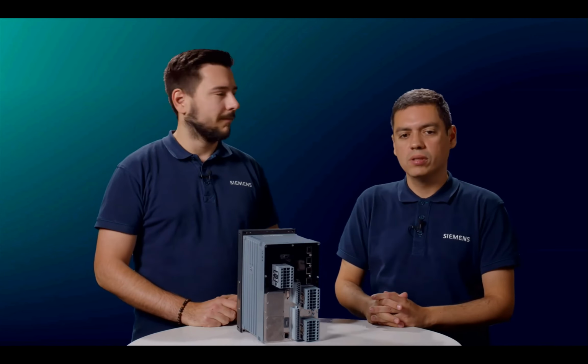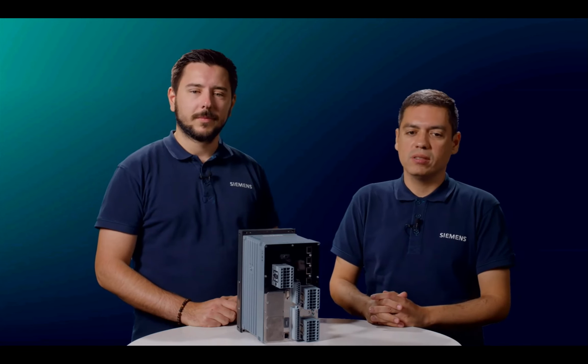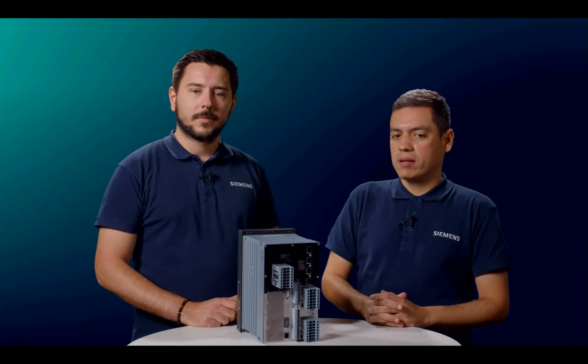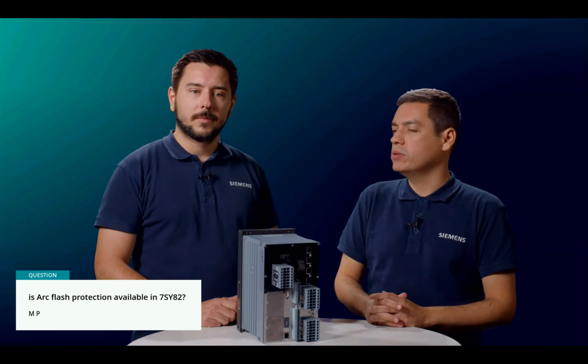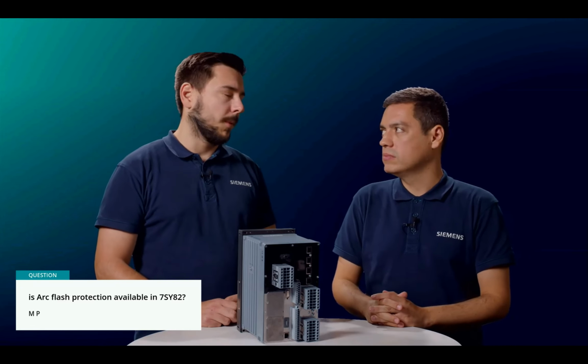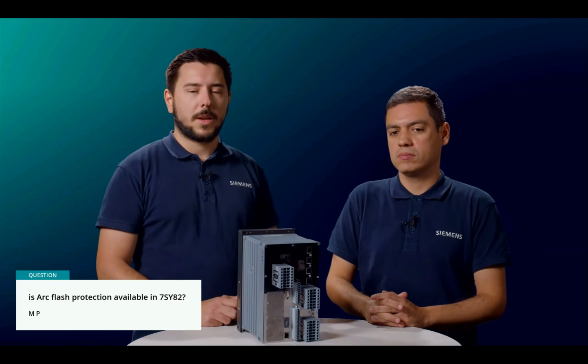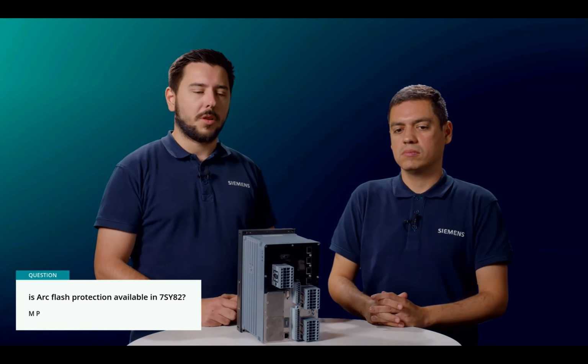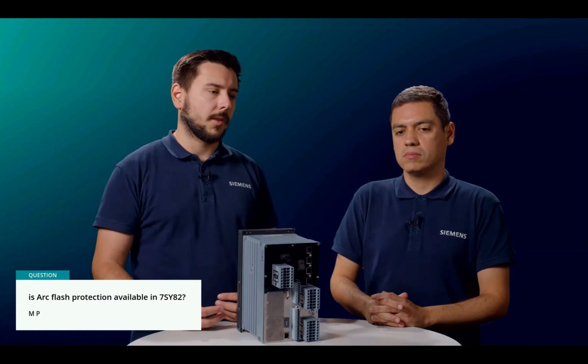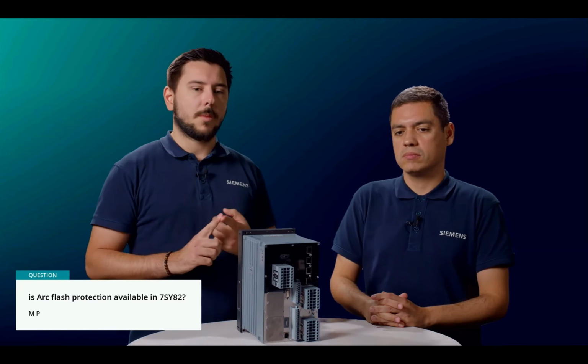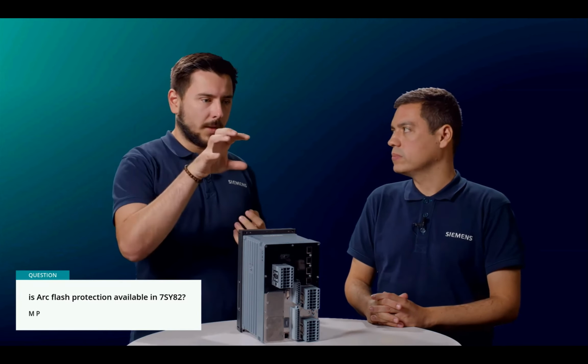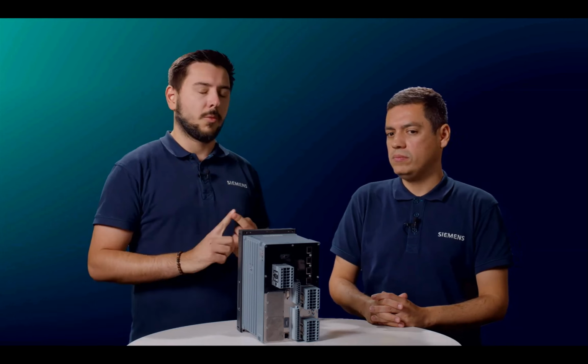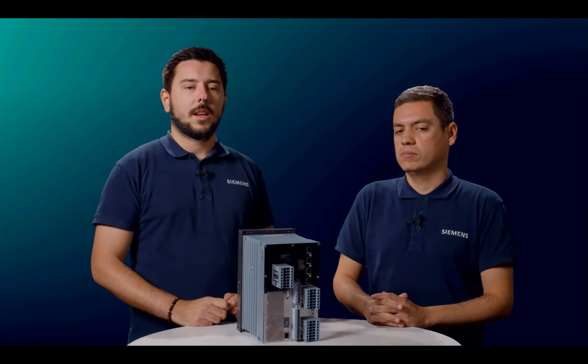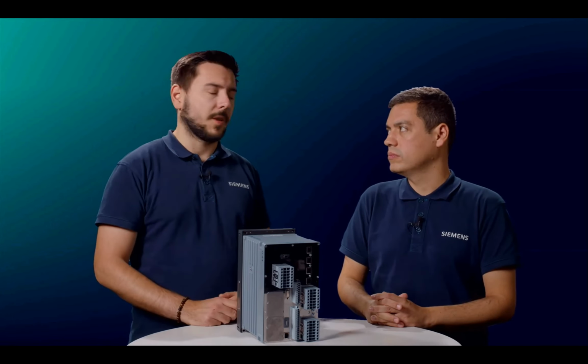One question about arc flash protection. Will this function be available in the 7SY82? Unfortunately, not from the beginning. This is what you already mentioned earlier. We are not supporting any of the analog inputs, so no temperature measurement, and the analog plug-in modules, the NIE modules, are not working yet, and therefore the arc flash protection module is also not included.